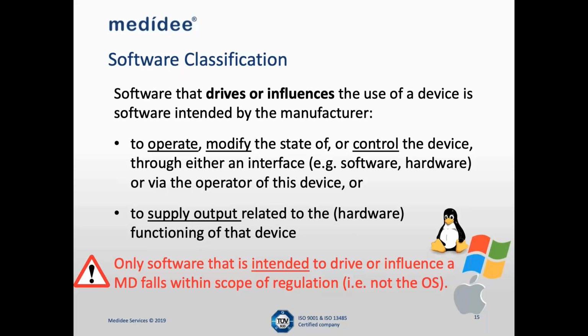So, for example, when you have a CT console or a remote control console for robotic surgery, you have a hardware device, which is a console or the remote, and the interaction with the software is driven through it. The software which is inbuilt or integrated within the medical device is helping to perform the robotic surgeries and is driving the clinical procedures. It is in a position to interface with the operator or via another hardware or another software. So it is important to understand when your software is driving or influencing the use of the device.